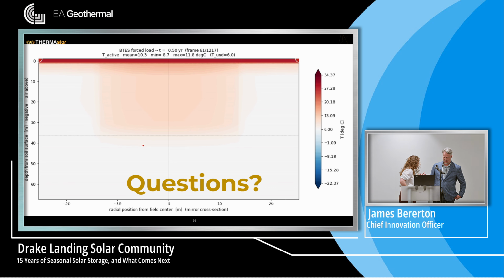Just curious, we know about thermal conductivity in different kinds of rock sources. I'm wondering if there's a preference of rock material you're drilling through or using for conductivity. It's a little less sensitive than typical geo-exchange. In geo-exchange, if you have low conductivity, that's really bad for you. In the borehole thermal energy storage case, it's bad to get the heat out, but it also doesn't lose at the periphery. So low conductivity gives us higher round-trip efficiencies, but we still prefer high conductivity rocks, because our challenge is that we make the field smaller, so we don't have enough surface area to get the heat out during peak times. So we'd rather have high conductivity rock, and we focus on the borehole heat exchangers to make them very low resistance. That gives us the thermal power we need in the short term.